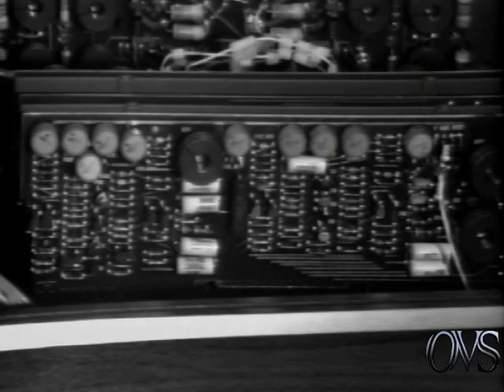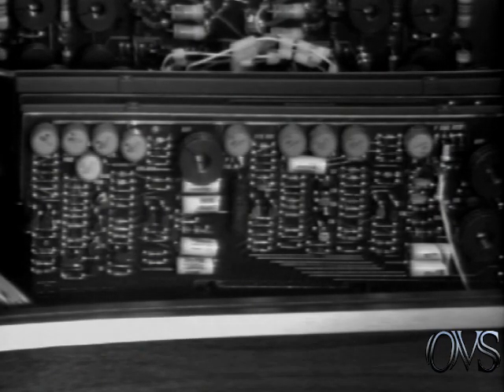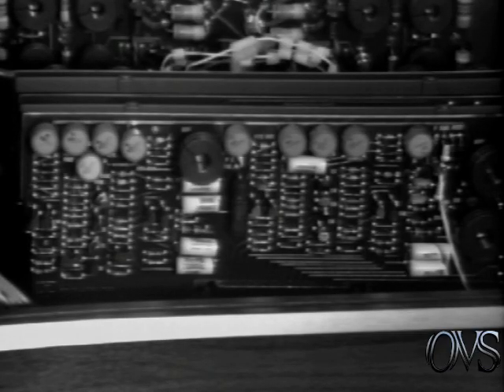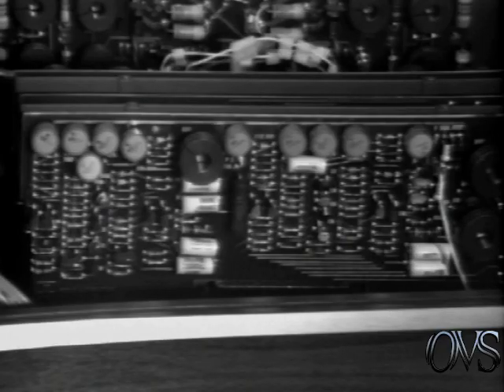Move the spot to the center of the screen along the X-axis and adjust X-axis astigmatism adjust number 2 and X-axis focus adjust number 2 for the best appearing spot. Now move the spot halfway toward center screen along the Y-axis and adjust Y-axis astig adjust number 1 and Y-axis focus adjust number 1 for best spot. Lastly, position the spot at center screen and adjust Y-axis astigmatism adjust number 2 and Y-axis focus adjust number 2 for best spot.